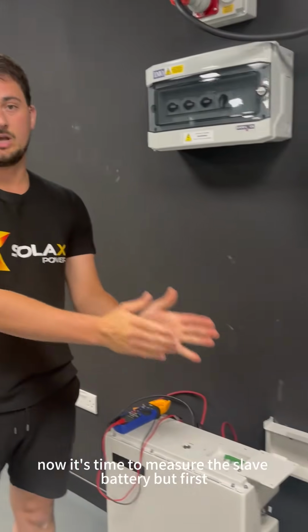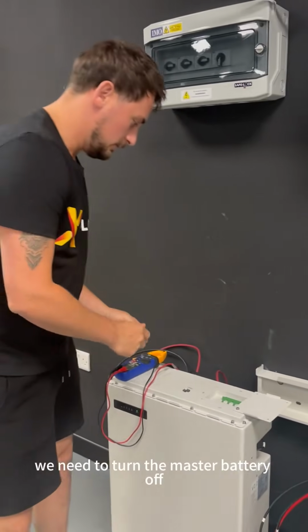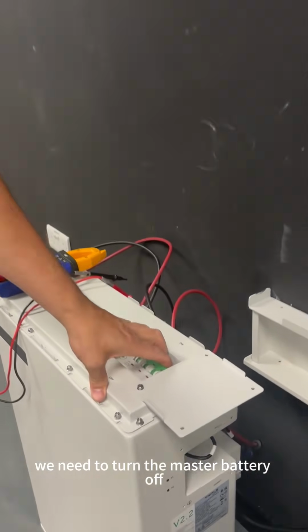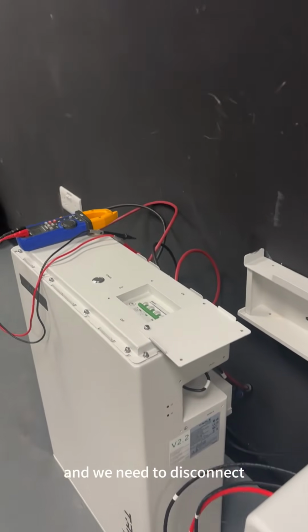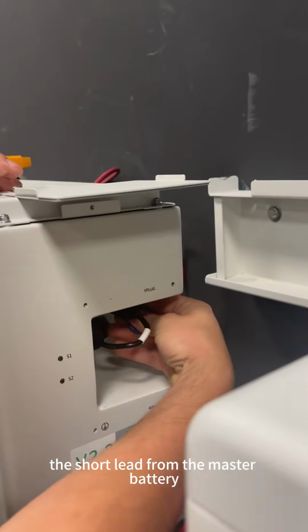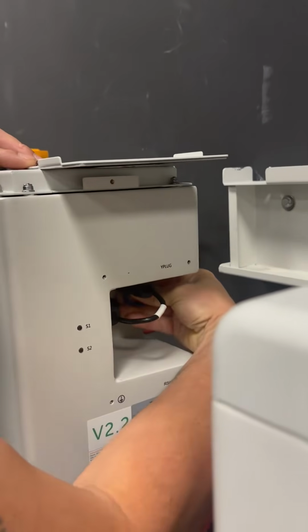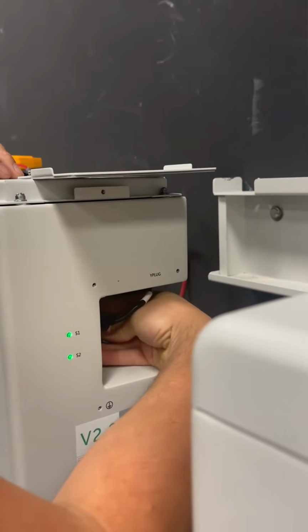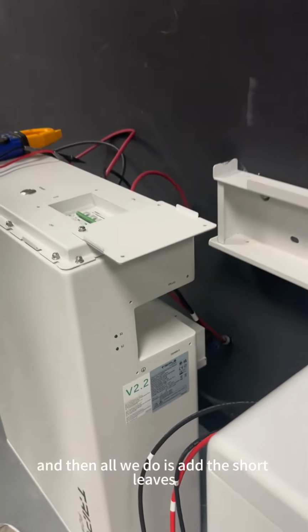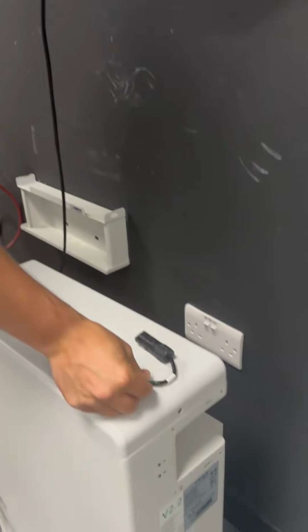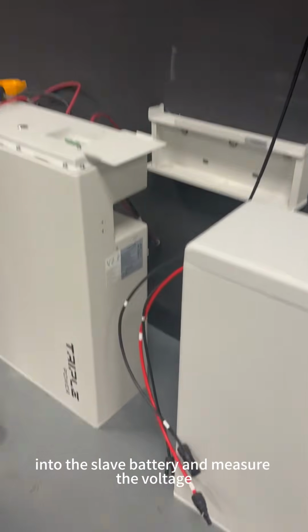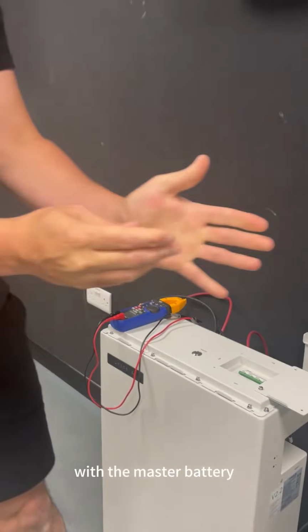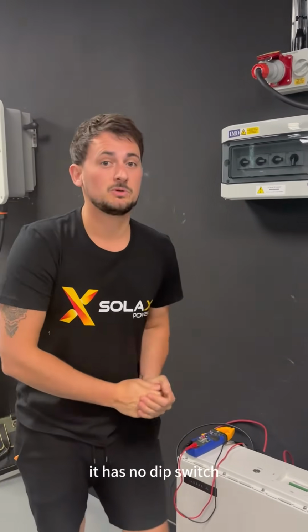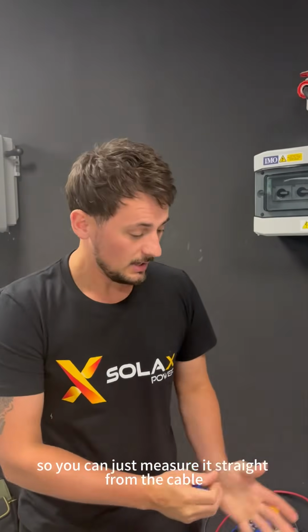Now it's time to measure the slave battery. But first, we need to turn the master battery off. And we need to disconnect the short lead from the master battery. And then all we do is add the short lead into the slave battery and measure the voltage just like we did with the master battery. But because it's a slave battery, it has no dip switch, so you can just measure it straight from the cable and take it from there.